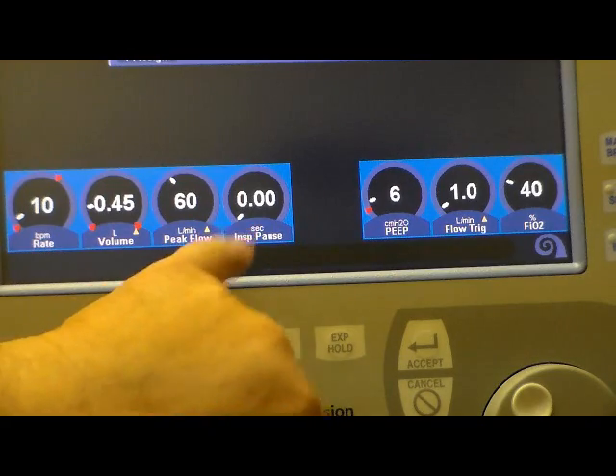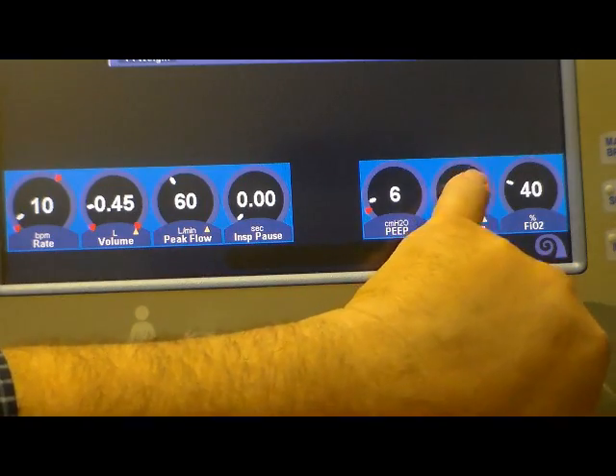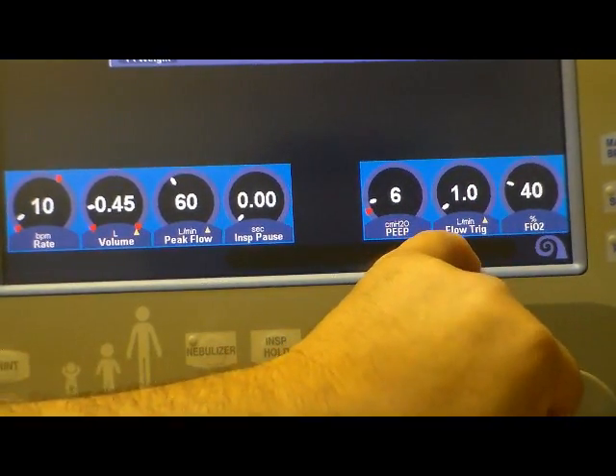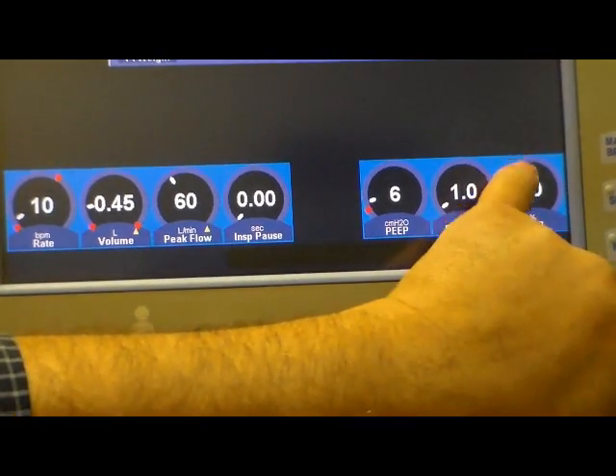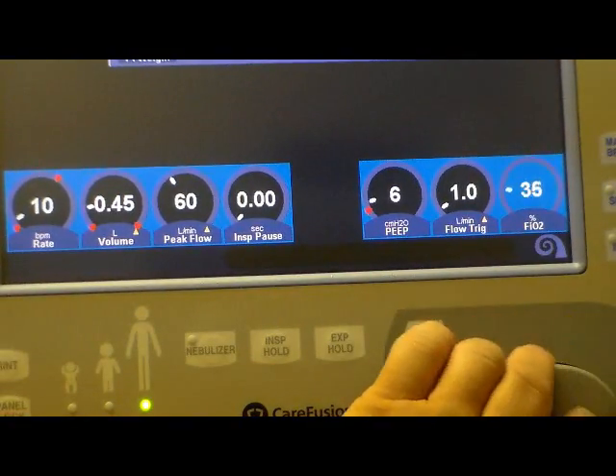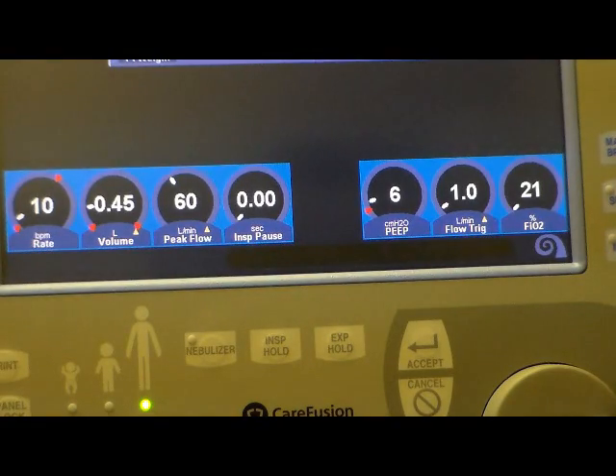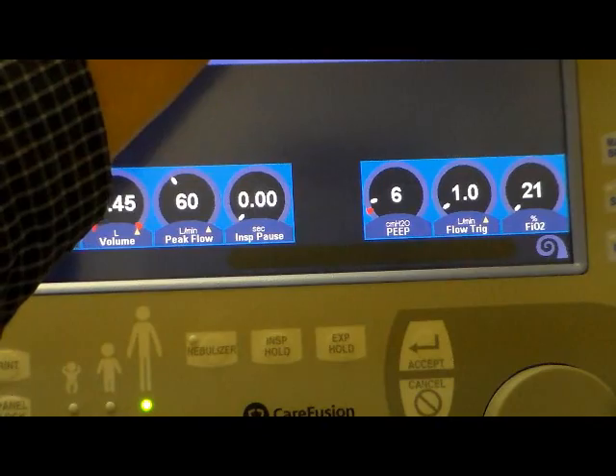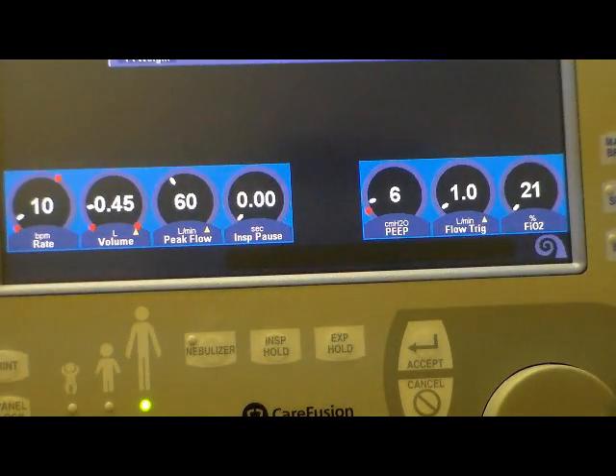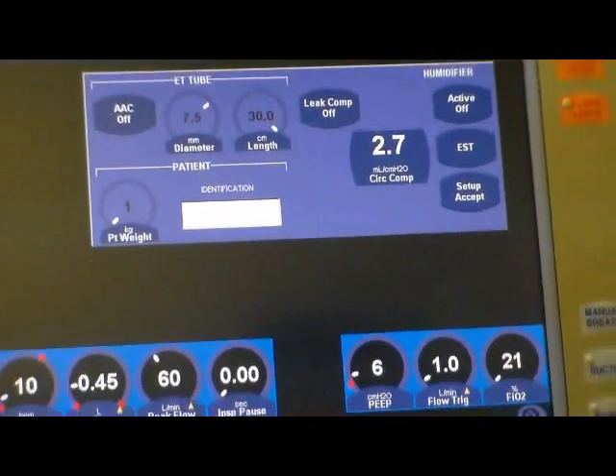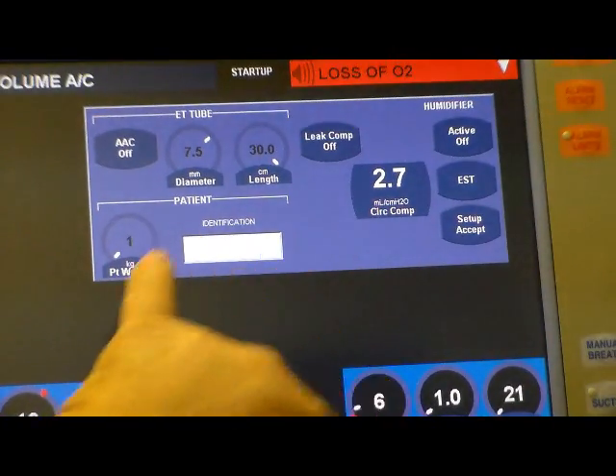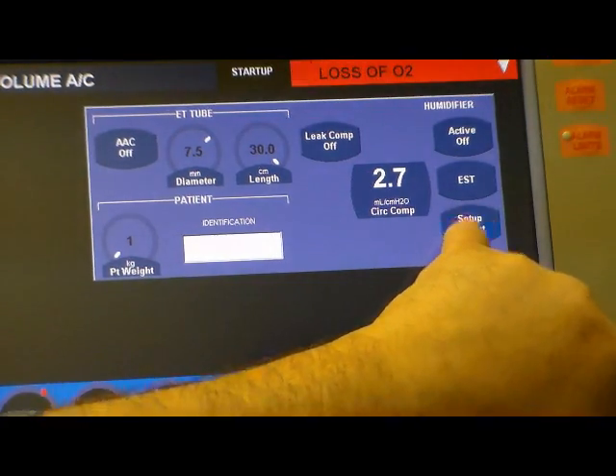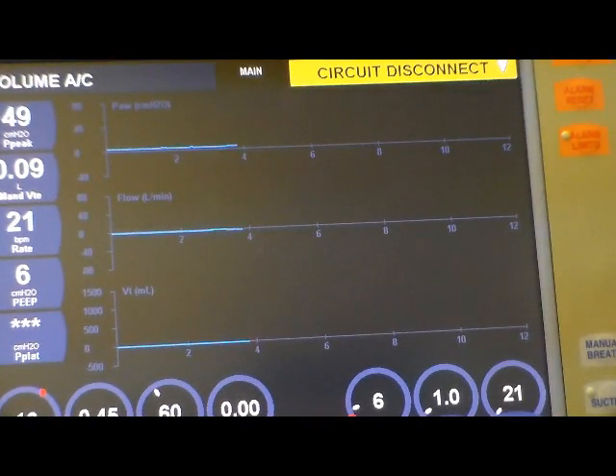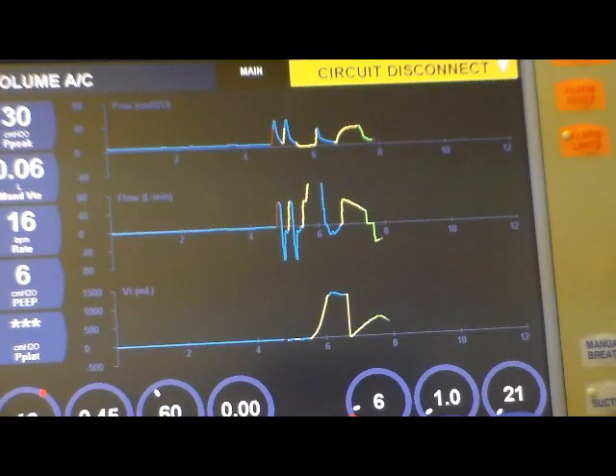Now we also have liter flow, we have inspiratory pause, we have PEEP, we have inspiratory trigger. We're on liters per minute, so that's a flow triggering, and we have our FiO2. Same loss of oxygen, so let's go up there and turn that down to 21. And that will make the oxygen happy. And now we're going to go into our alarm limits by pressing, let's see, okay, now we have everything set up. We like what we've set for the ventilator, so we're going to just simply go with setup, accept the setup, and I'm going to put it on a test lung to ventilate.